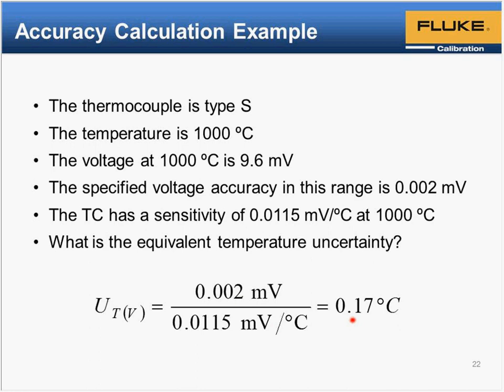So 2 microvolts on a thermocouple at 1000 degrees C gives you a 0.17 degrees C temperature. So noble metal thermocouples like Type S can be challenging to measure.